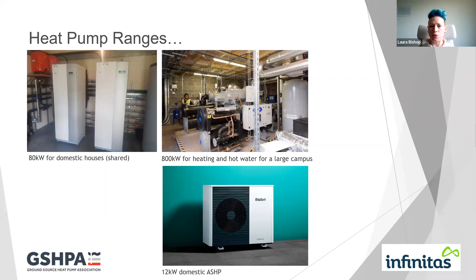But as I mentioned towards the start, heat pumps are really flexible. So you can have the size of a heat pump anything from a 3 kilowatt unit, a little tiny shoebox unit that might go into a small flat, all the way up to 8, 9, 10 megawatts plus, especially when you are cascading heat pumps together in both air source and ground source. Although when you start to get to the much bigger commercial systems, ground source starts to make a lot more sense. The resource you can use is really flexible too.